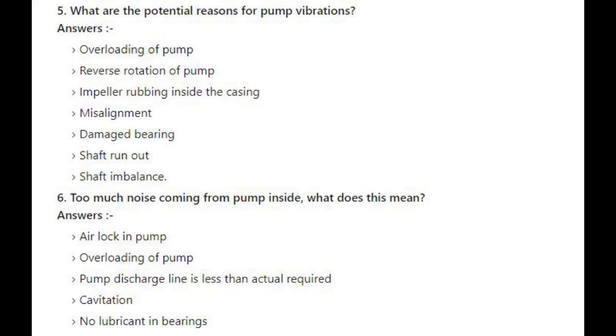Number 6: Too much noise coming from inside the pump — what does this mean? Air lock in pump. Overloading of pump. Pump discharge line is less than actually required. Cavitation. No lubricant in bearings.